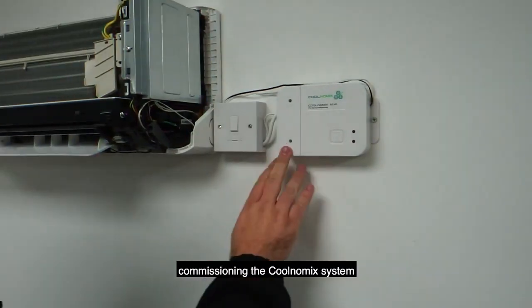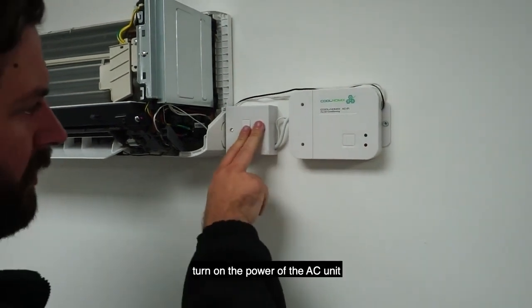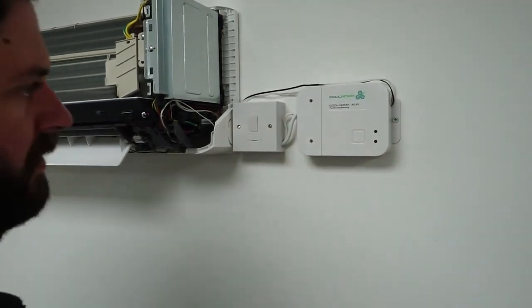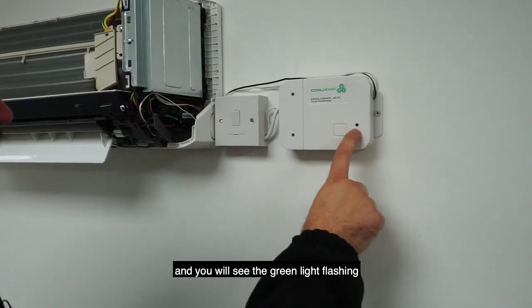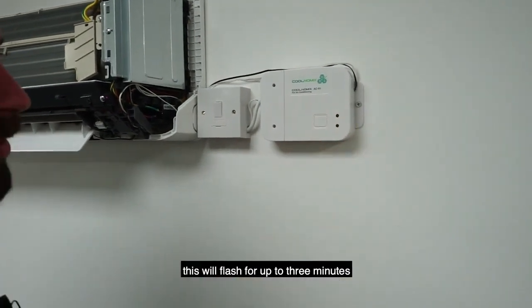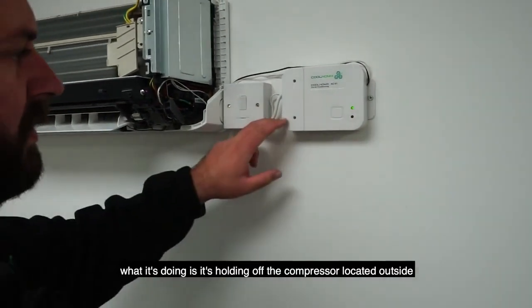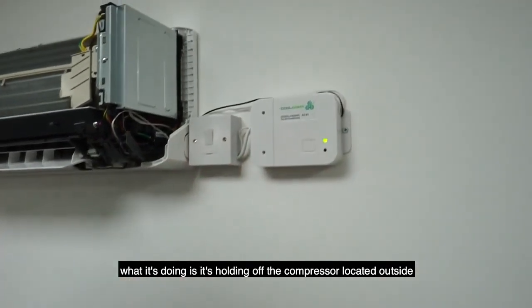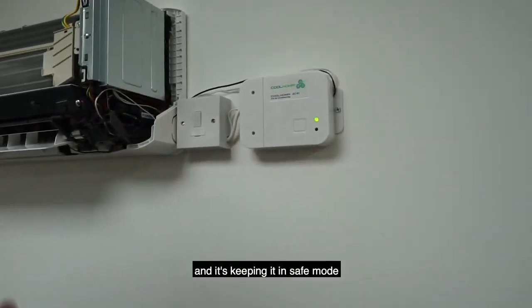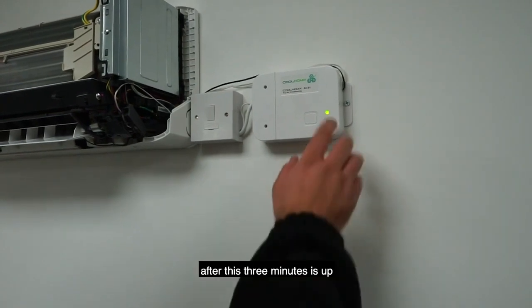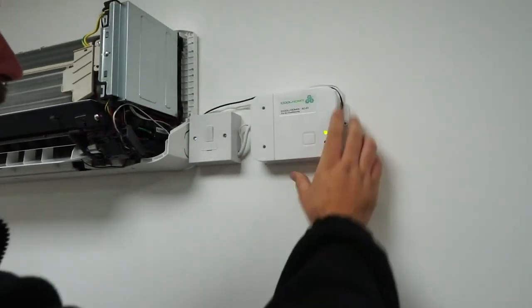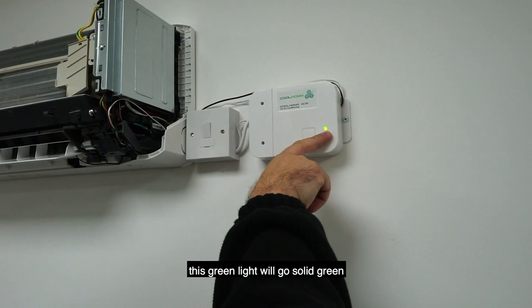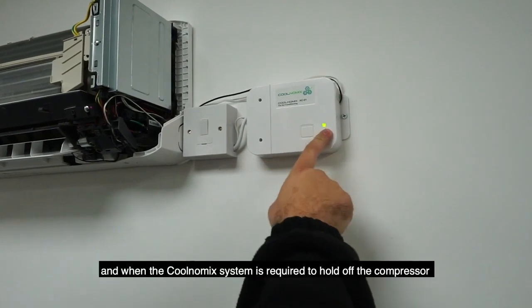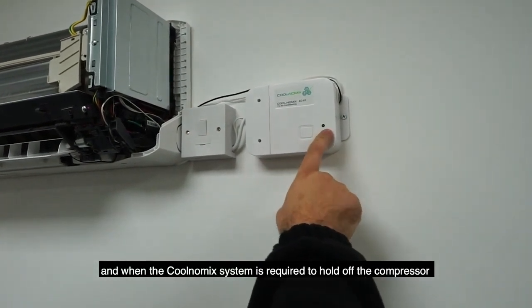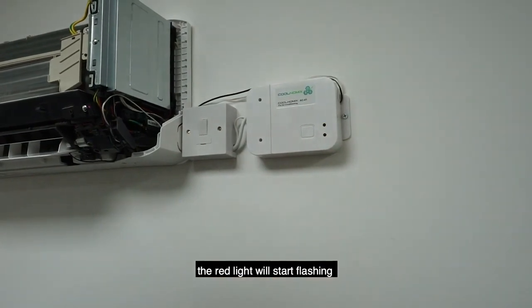Okay. Commissioning the Coolnomix system, turn on the power of the AC unit and you'll see the green light flashing. This will flash for up to 3 minutes. What it's doing is it's holding off the compressor located outside and it's keeping it in safe mode. After this 3 minutes is up, this green light will go solid green, and when the Coolnomix system is required to hold off the compressor, the red light will start flashing.